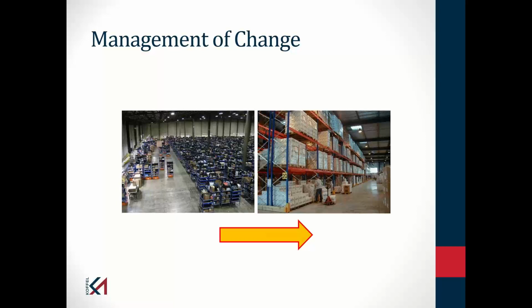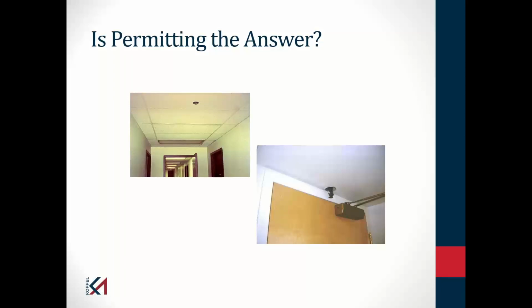If you are using encapsulated storage, where I now wrap the product on that pallet load in plastic, that changes my sprinkler design criteria. So there's a lot of things that can change in a storage occupancy. What might appear to be a very subtle change could require a reevaluation of the sprinkler system. And while permitting is an answer for many of the situations, some of the things I just talked about, changing containers, changing the commodity that you're storing in the warehouse, you most likely are not getting a building permit for that. So there is no regulatory agency that's overlooking that.